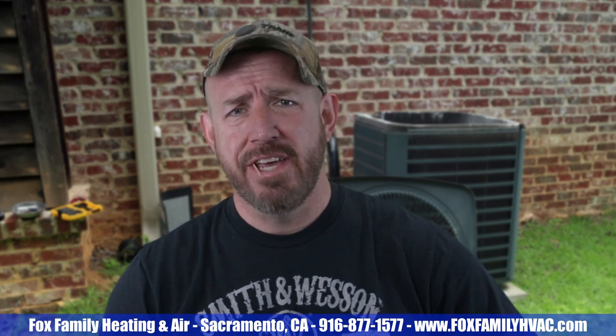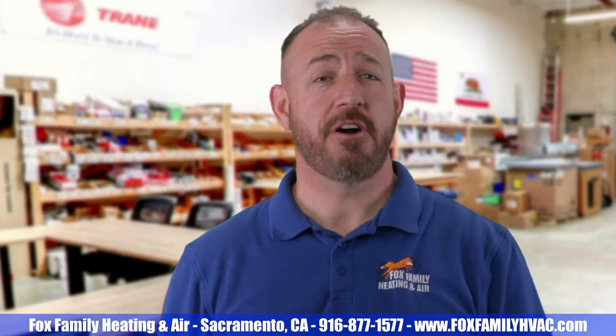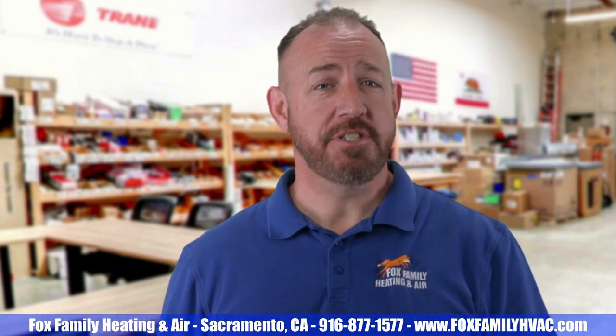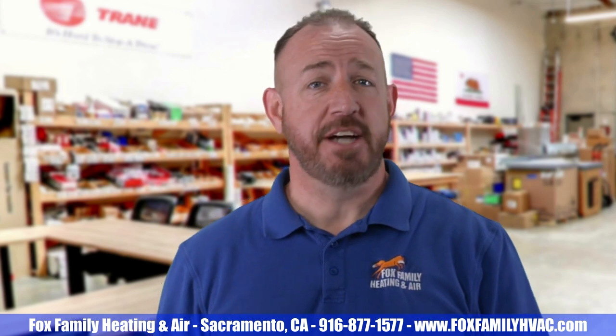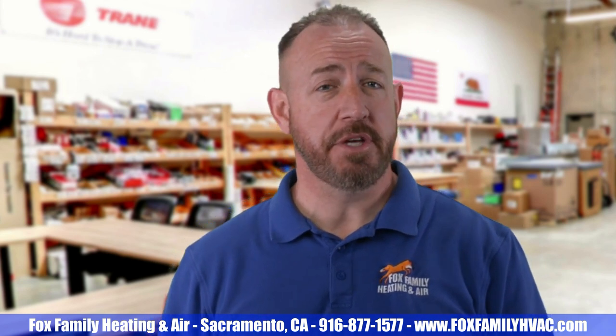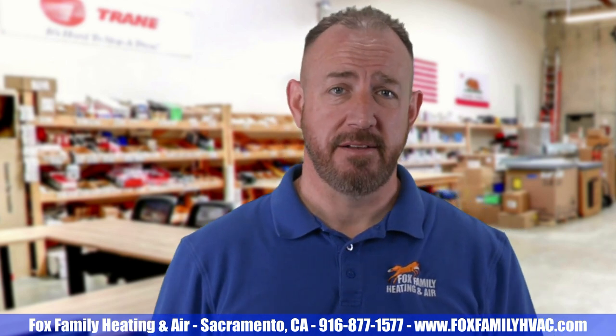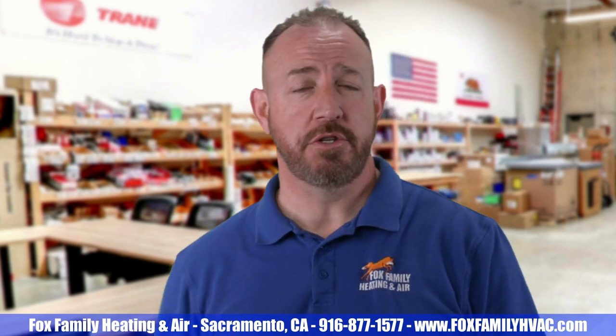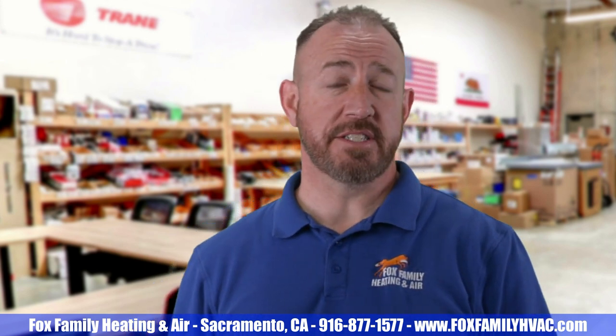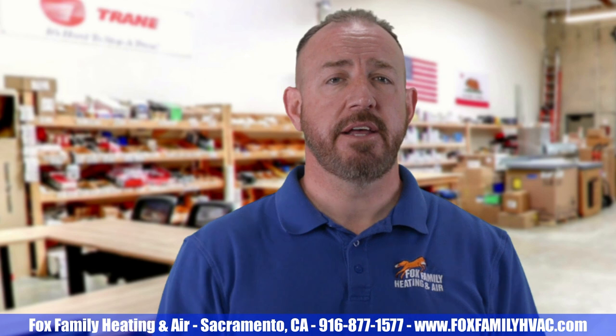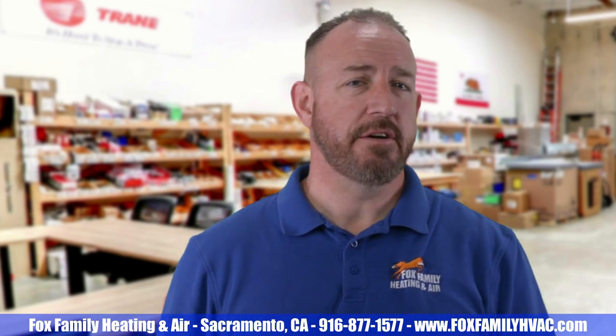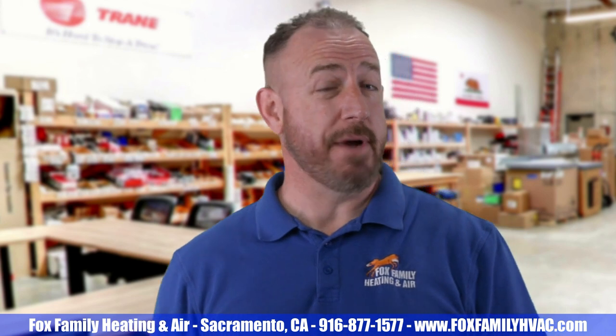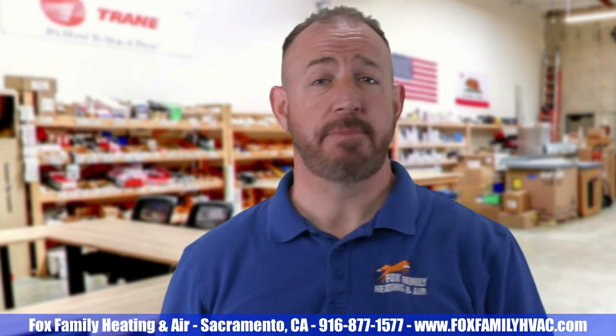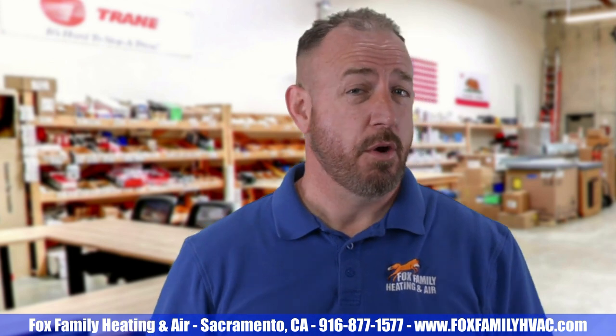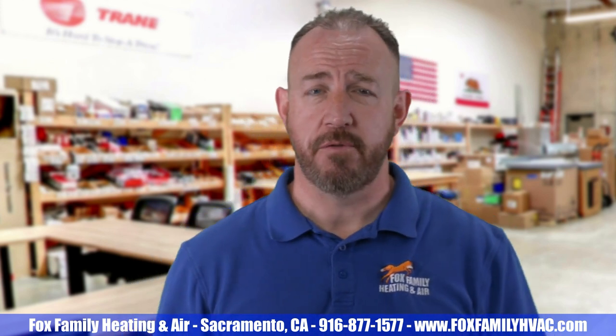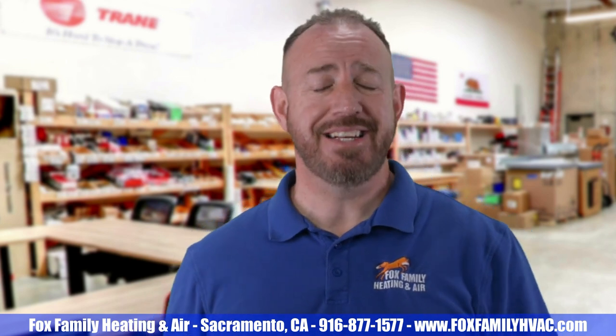R22? That stuff's not even legal anymore. No, R22 is not illegal. But I will tell you this, it's not getting any cheaper. The price of R22 rose about 400% in the 2 years following COVID-19, with no end in sight. As the current supply of virgin R22 diminishes, old, recovered R22 from existing decommissioned units is being cleaned and recycled for future use. You have to consider that the last R22 complete systems were installed around 2010, and systems are designed to last about 15 to 20 years. So R22, or even a less expensive substitute refrigerant like R458A, Bluon, will be around at least until 2030.